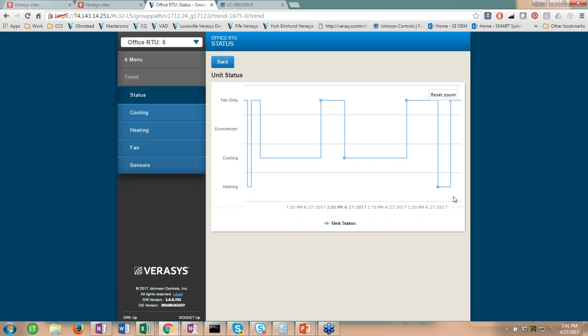Even with the rooftop on a third party here, we have a certain amount of trends pre-configured. I'll go into status, and we could see how many times this unit has been cycling on and off between cooling and fan throughout the past 24 to 48 hours. These trends are already pre-programmed; you just turn on the controller and it starts trending these values automatically, no programming or configuring needed. This is very important information when maintaining a system.